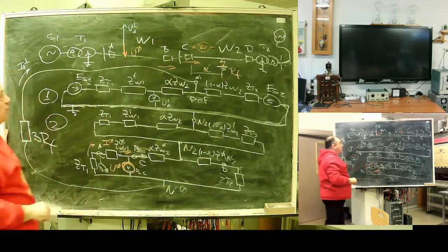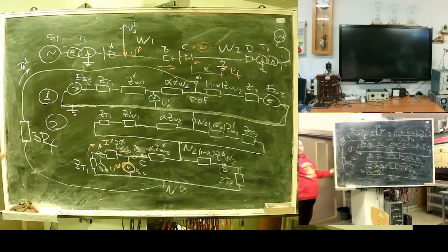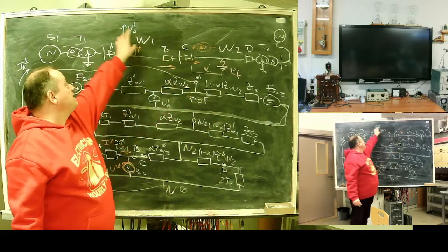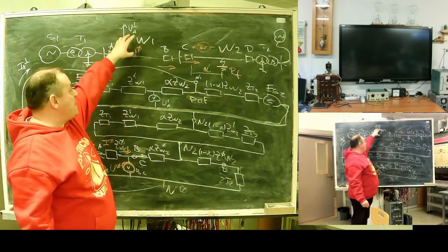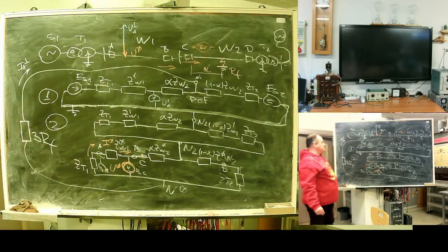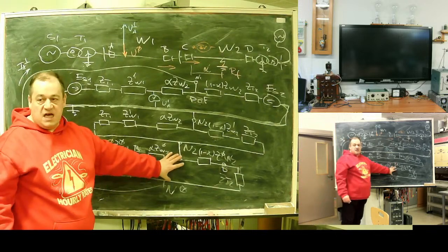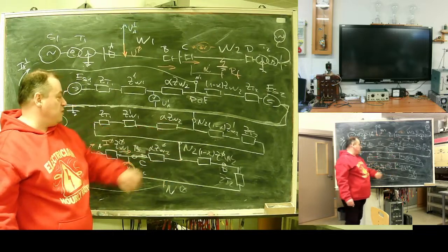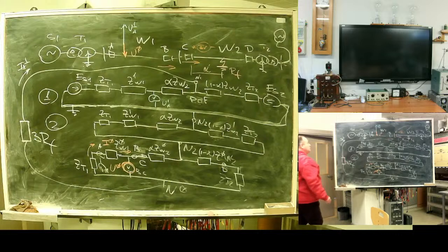At a point of fault, sum of voltages is zero. So here, at the point of fault, direct sequence voltage equals the sum of zero and negative sequence voltage. Negative will be smaller because resistance of this network is approximately 3 times higher than this network. Your zero sequence voltage looks down.